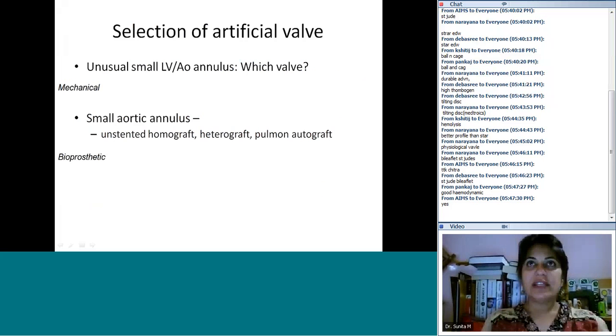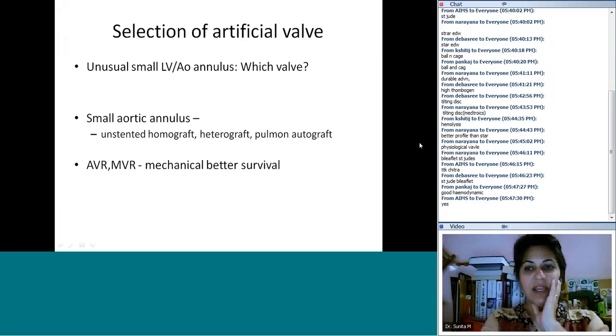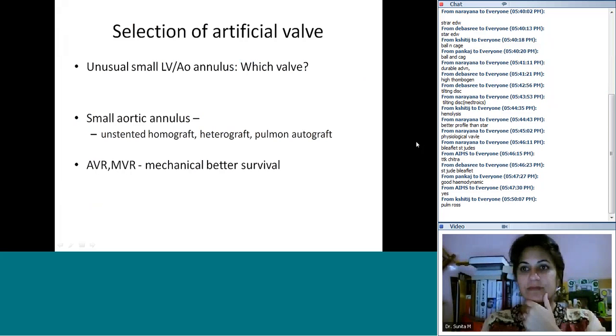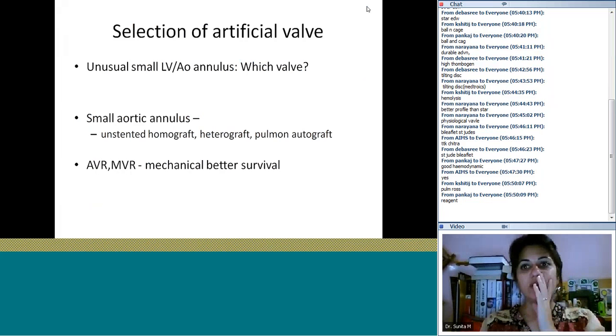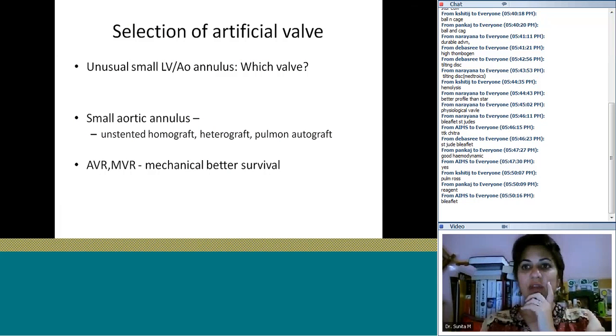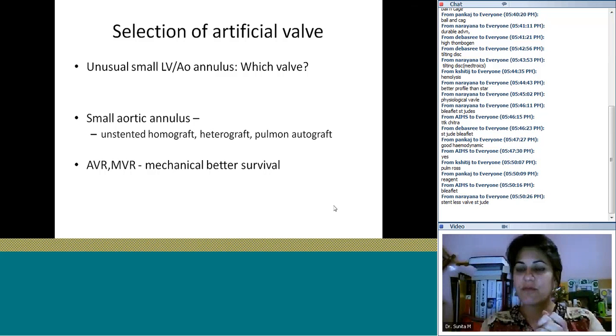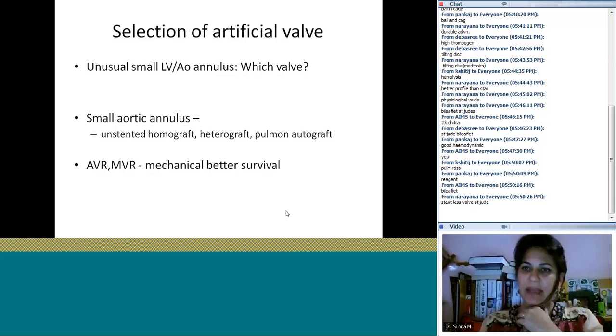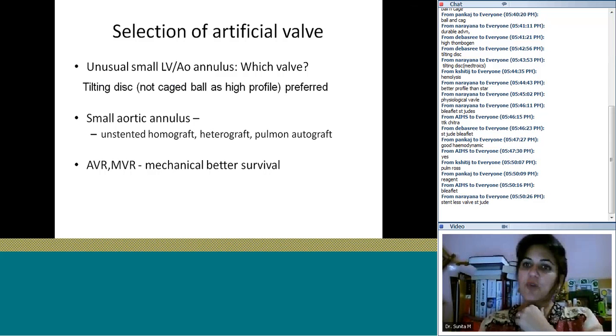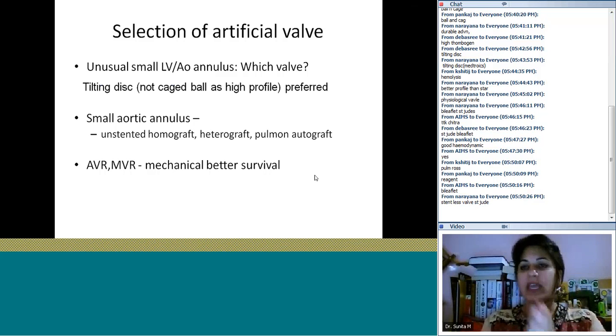Now, selecting an artificial valve: if you have a very small aortic annulus, which valve would you choose and which would you avoid? You would not choose the caged ball due to its very high profile. You would choose either the tilting disc, which has a very low profile suitable for small annuli, or the bi-leaflet St. Jude, which also works well in small sizes.